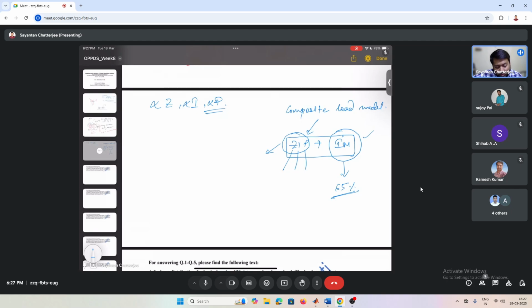So my point is that mostly the system would be inductive, with more prominence of inductive reactance. To benefit the customer voltage profile, we install shunt capacitances in the system. There won't be cases where we have both inductive and capacitive loads in the system, for which we'd incorporate reactors. But in transmission systems, low loading cases occur where shunt reactors or series reactors need to be incorporated - these are special scenarios, not practical in normal operation. So in actual practice, the loads would be lagging in nature.